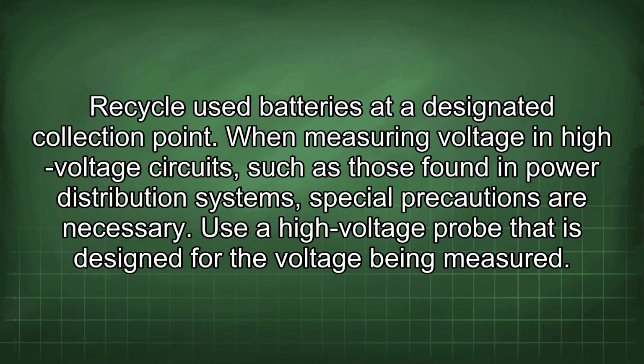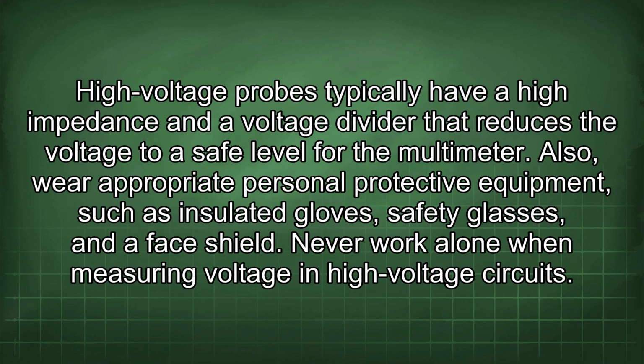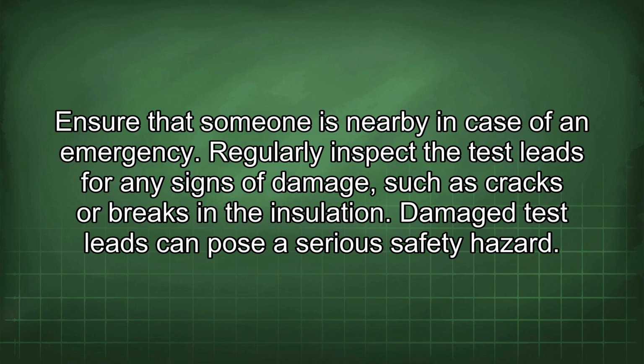When measuring voltage in high-voltage circuits, such as those found in power distribution systems, special precautions are necessary. Use a high-voltage probe that is designed for the voltage being measured. High-voltage probes typically have a high impedance and a voltage divider that reduces the voltage to a safe level for the multimeter. Also, wear appropriate personal protective equipment, such as insulated gloves, safety glasses, and a face shield. Never work alone when measuring voltage in high-voltage circuits. Ensure that someone is nearby in case of an emergency.